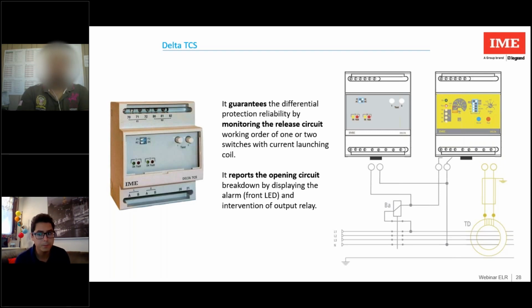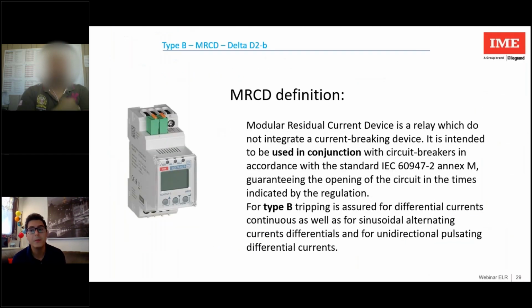And for the type B, IME also recently added a type B model. I remember that type B tripping is assured for continuous differential current, as well as for sinusoidal alternating differential currents and for unidirectional pulsating differential current. Our device is a modular residual current device, which does not integrate a current breaking device. It is intended to be used in conjunction with the circuit breaker.